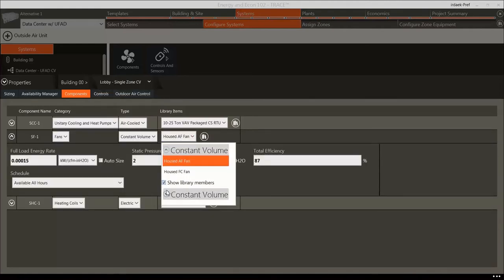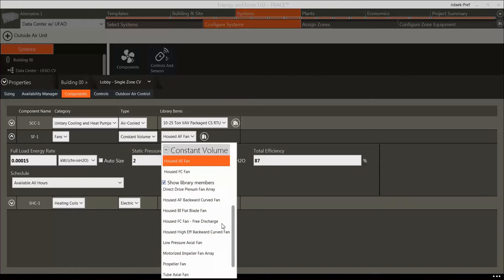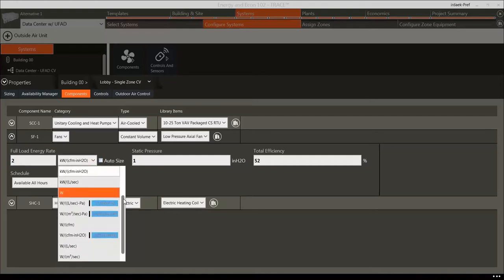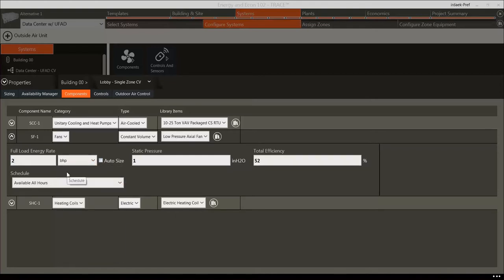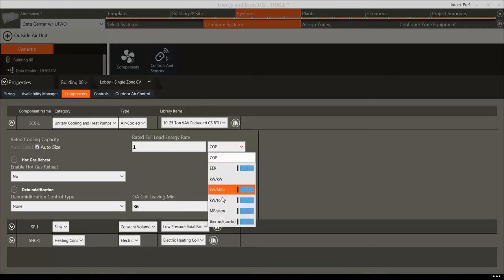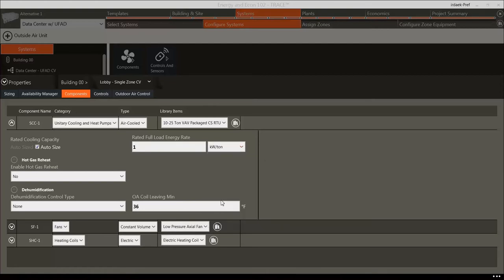In the Components tab, we can also view and modify the coil parameters. Let's double-check some of our inputs from Load Design. In the Properties for the Lobby System, verify that we have a DX coil selected — this is represented by the Unitary Cooling and Heat Pumps category. Then set the Cooling Coil Rated Full Load Energy Rate to 1 kW per ton, which represents the energy rate for the unitary rooftop that cools the lobby. Make sure the heating coil is a standard electric coil.